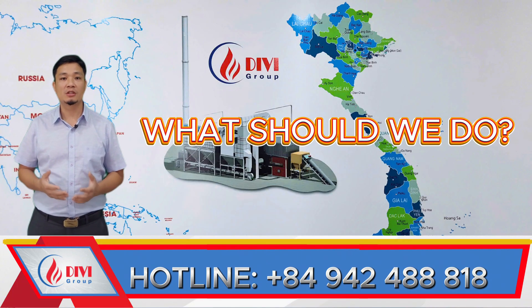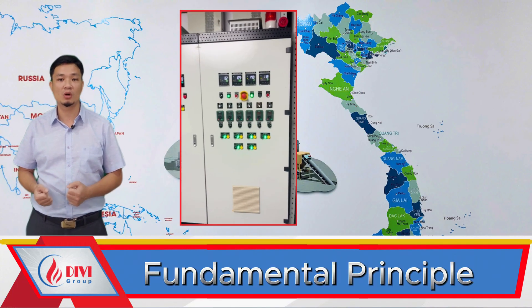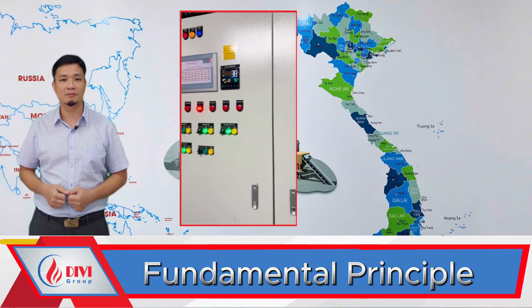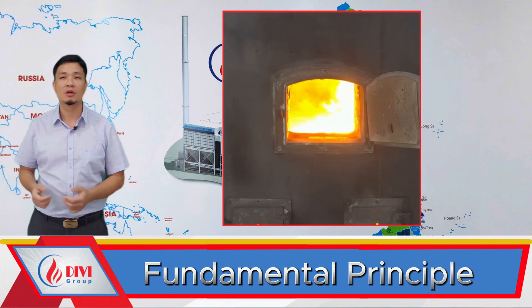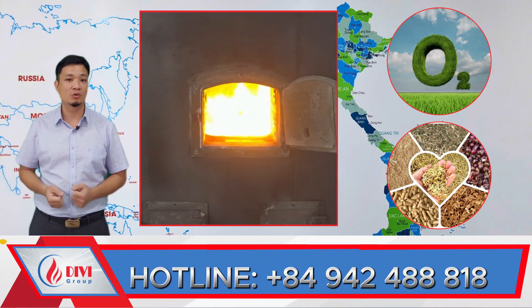So what should we do in this case? Here's the one core principle you must remember: if all other safety systems, such as low water alarms, phase loss protection, etc., are operating normally and only the low pressure alarm is triggered, then the most common cause lies in the fuel combustion process. This combustion process is governed by two factors: oxygen and fuel.